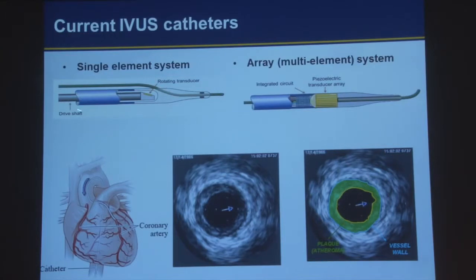In all cases, the first thing that the operator does is thread a guide wire first, and the catheter, or even the angiography X-ray catheter, is threaded on that guide wire. So that's why I'm just trying to make a note of that. If you can put something on the guide wire, you actually improve things a lot in terms of operation.